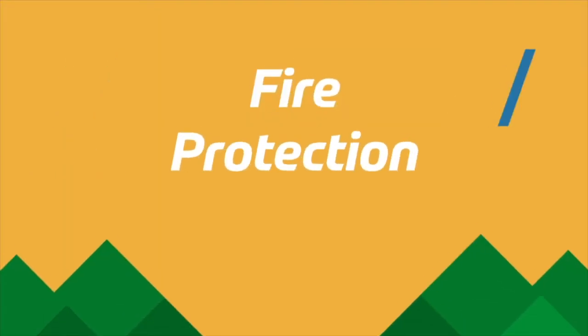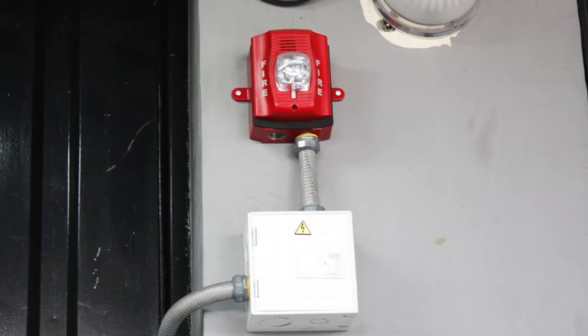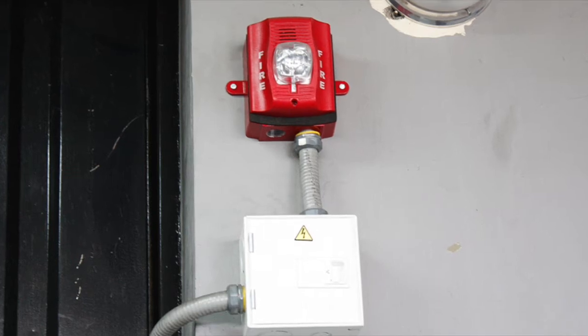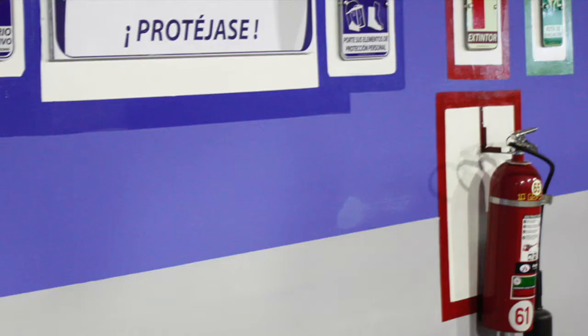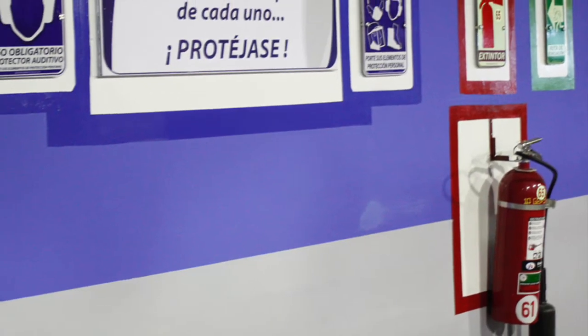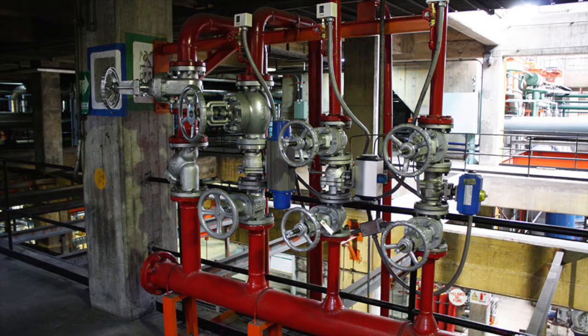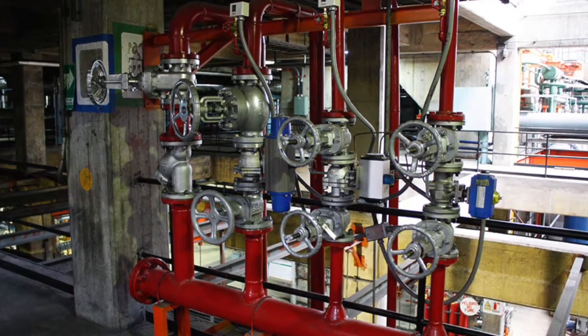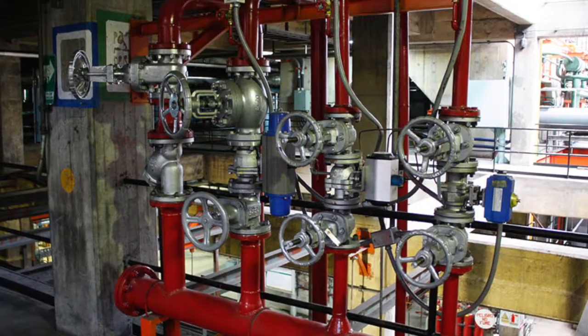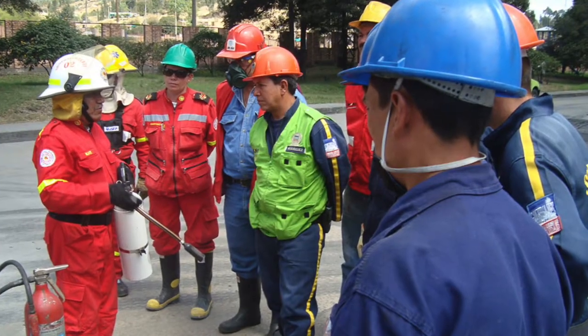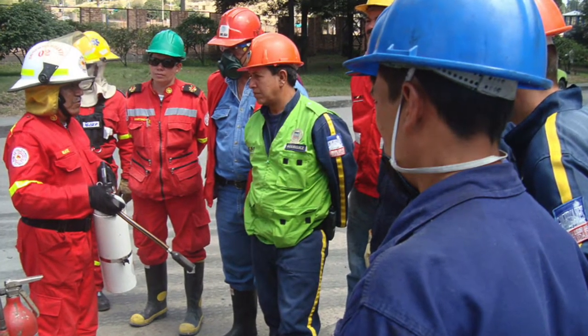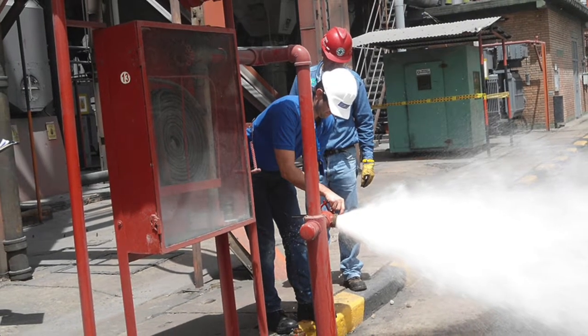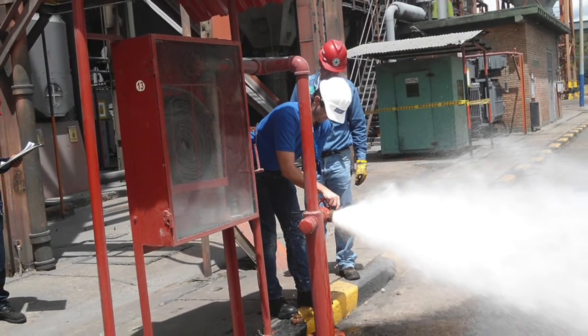Fire protection. There are fire protection systems such as a hydraulic network with 37 fixed outlets and 14 monitors and electric pumps, protection of over 100 extinguishers, water deluge systems for transformers and oil tanks, relay room, battery room, and diesel generator room. The power plant has an AFFF foam suppression system for the boiler fuel tanks and pumps.